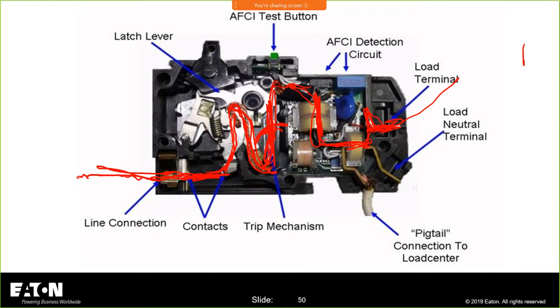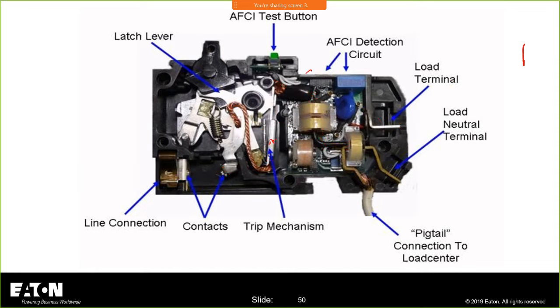Now, if you were doing thermography, I've gotten some questions on this. They'll say, we put a thermal camera on your circuit breaker, and we noticed that the temperature is very high on the front of this breaker, and they want to know why. And they'll say, well, that's a bad thing. Well, it's not a bad thing, because when current is flowing, you have a couple points in here.